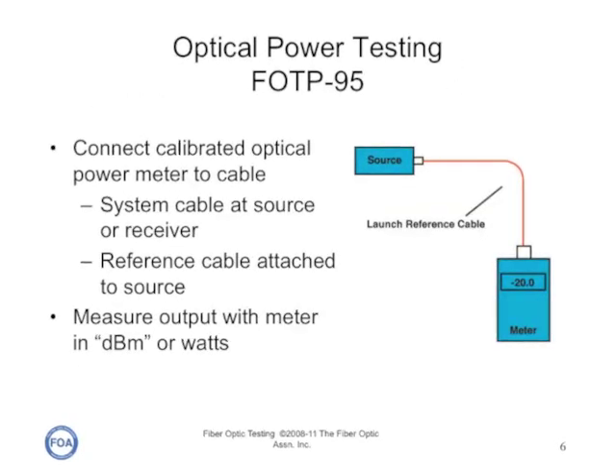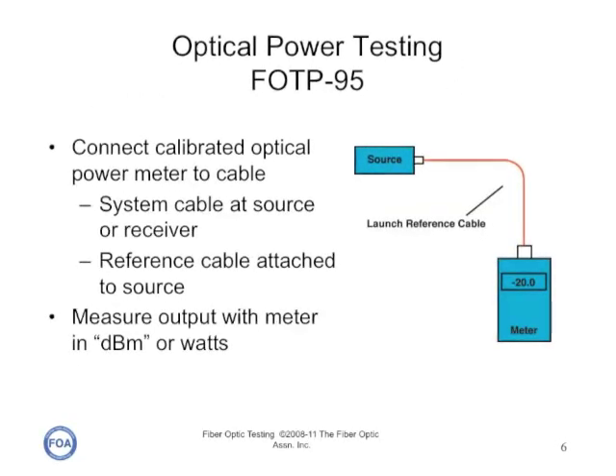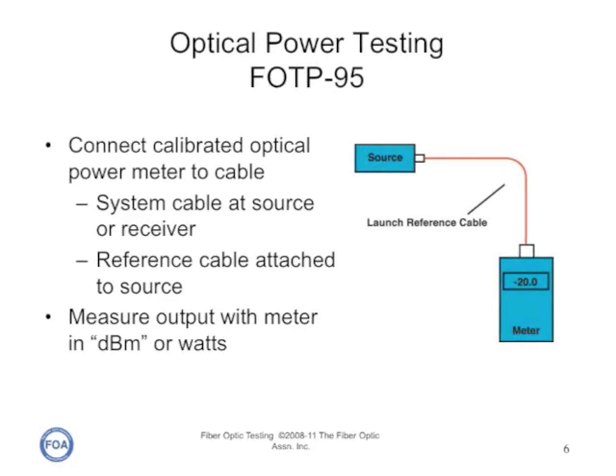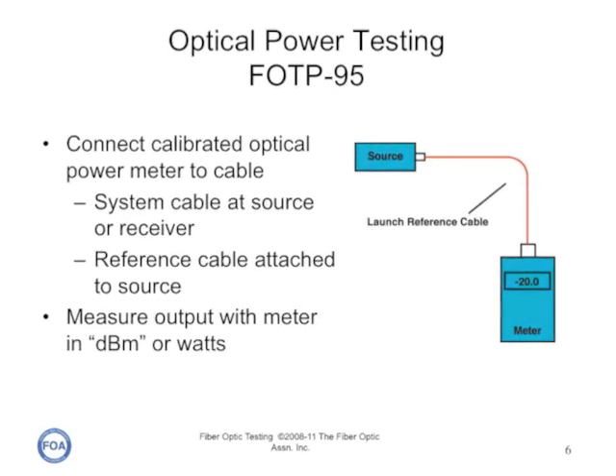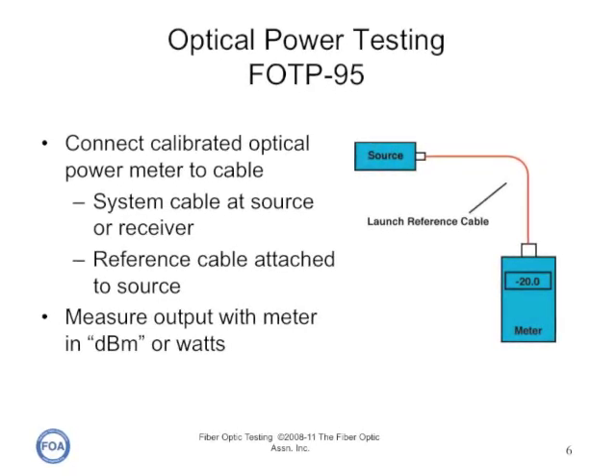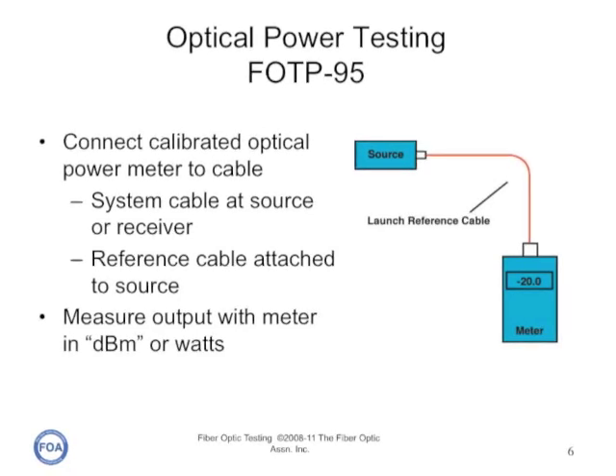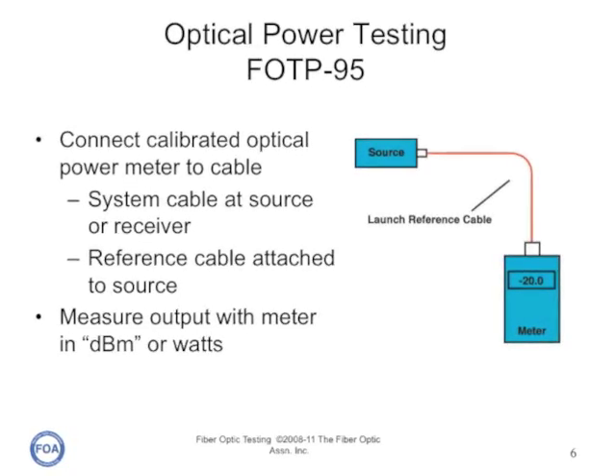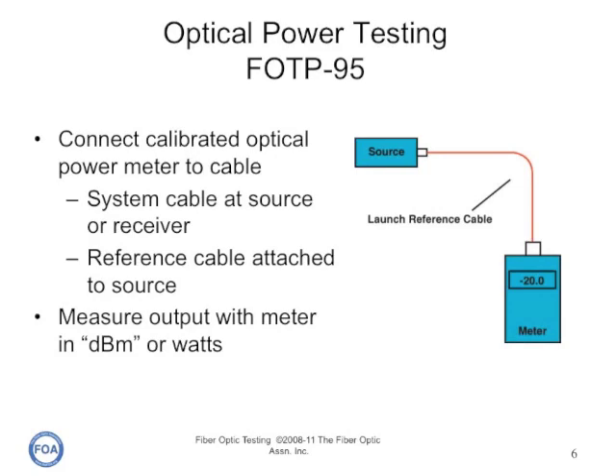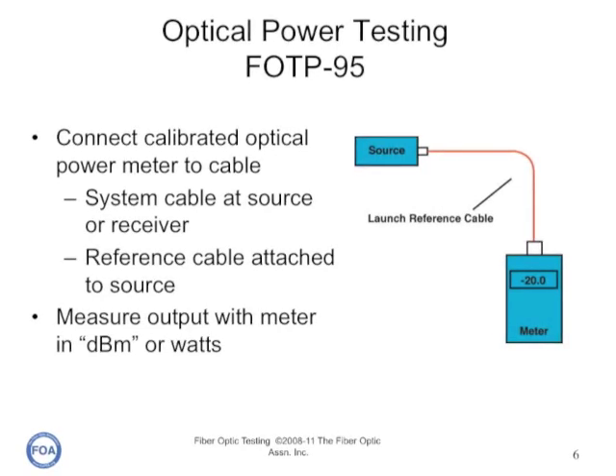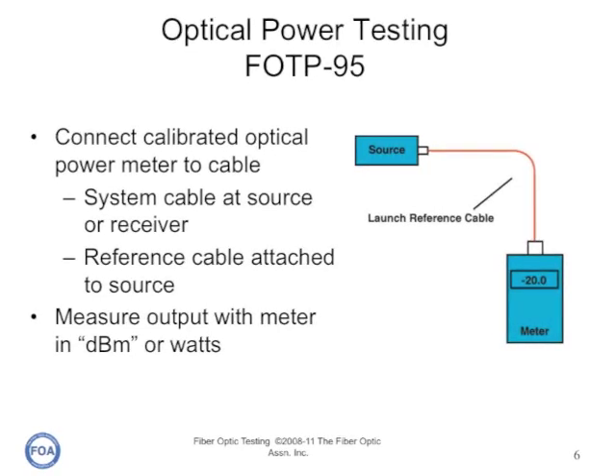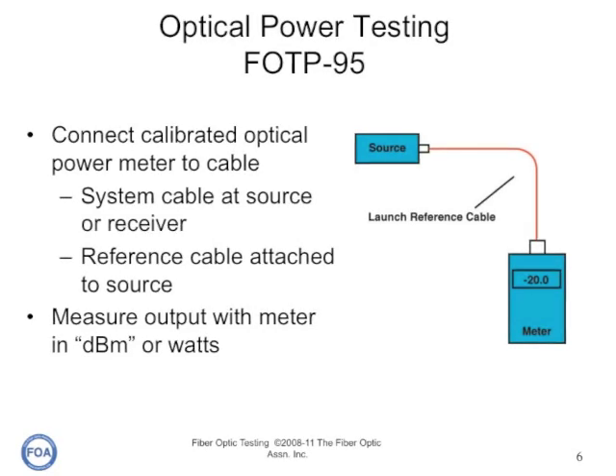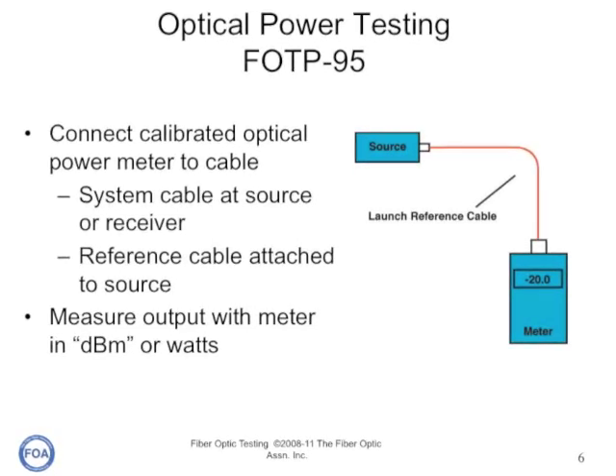The standard way of measuring optical power is covered in a TIA standard, FOTP-95, and it's accepted internationally. Basically, we connect a calibrated optical power meter to the cable, set it to the correct wavelength, and measure the output in dBm or watts.